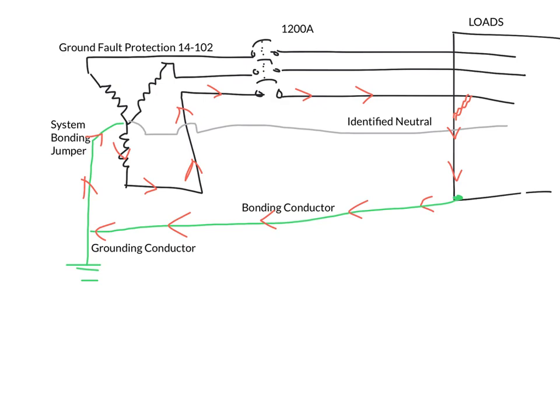One of the systems used to achieve ground fault protection is called the zero sequence method. Now, if you've ever taken your clamp-on ammeter and clamped it around a multi-conductor cable that was under load, you'd read 0 amps, and that's because the net current flow between the hot conductors and the identified neutral conductor should be 0 amps. There's a canceling effect there. So essentially we do the same thing. What we do is we place a big current transformer around all three phases and the neutral. Under normal conditions, that CT should see 0 amps, net zero current flow, because the phases and the neutral cancel each other out. But when a fault develops, current is no longer flowing back on the identified neutral conductor, it's now flowing on the bonding conductor. So the CT sees something other than 0, which in turn sends a signal to a relay to open up the circuit. And that's how ground fault protection is achieved.